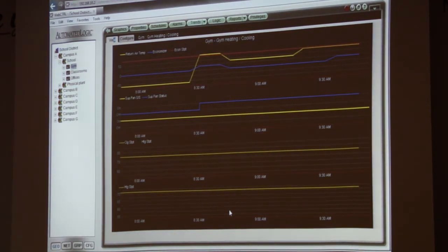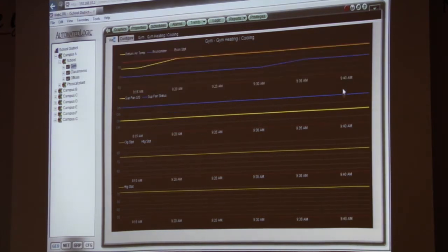So now if I see a problem with one section of it, I could say here, I see the problem happening right here. It looks wrong, like right about here. I could zoom in, and now everything will zoom in, and I can be looking at everything that happened. So yes, I can look at a graphic and see what's going wrong. Somebody tells me there was a problem with the unit. It happened about an hour ago, 2 hours ago. If I have this trend set up in such a way that I could track the air all the way through, in the order that the air handler is running it, I could just come here and zoom in and look at what happened right at that time.